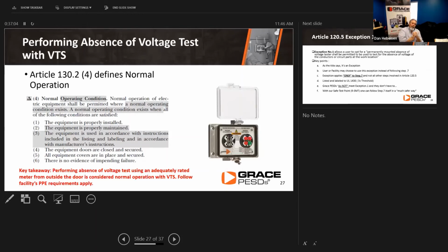Going back to Article 130.2, it defines the operating conditions. So when can this be used? Again, as was mentioned in the previous presentation, as well as I'm sure other things earlier this morning, the equipment is properly installed, the equipment is properly maintained, the equipment is used in accordance with the instructions included in the listing and labeling and the manufacturer's instructions. The doors are closed and secured. All the equipment covers are in place and secured, and there is no evidence of impending failure. The key takeaway here is performing an absence of voltage test using your voltmeter from outside the door is considered normal operation following the facility's PPE requirements.